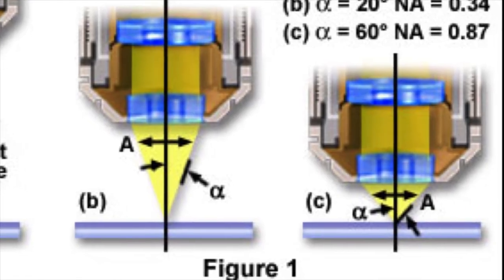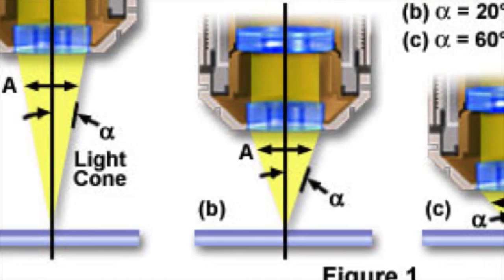Here we have three different objectives displayed on the screen. These are all the same magnification objective, but they all have improving numerical aperture. Notice that as the numerical aperture of the objective improves, the working distance is decreased. When you're working with a very high NA, high numerical aperture objective, your working distance is going to be markedly reduced.